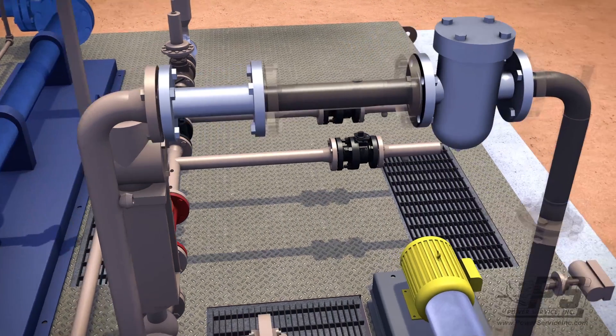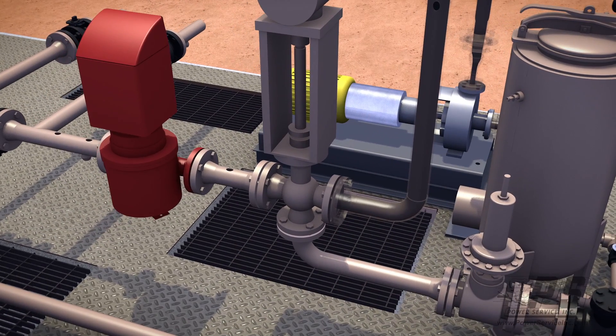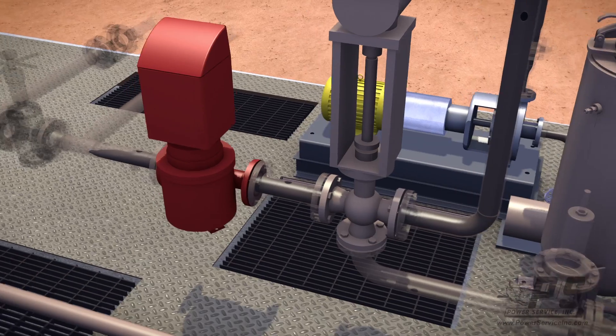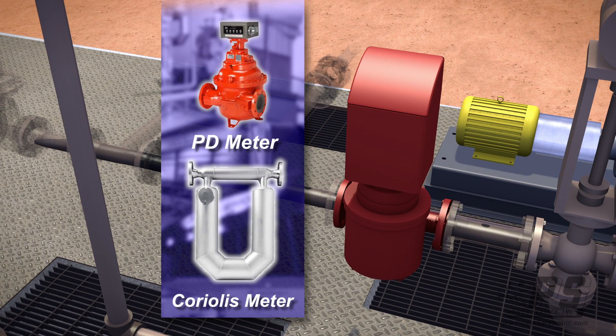As the oil goes through the system, it is continuously sampled before reaching the divert valve. If the BS&W determined that the oil did not pass preset specifications, the valve remains closed and diverts the oil back out to a bad oil tank. If it does pass, the valve opens and moves the oil through your choice of a pre-installed positive displacement or Coriolis meter.